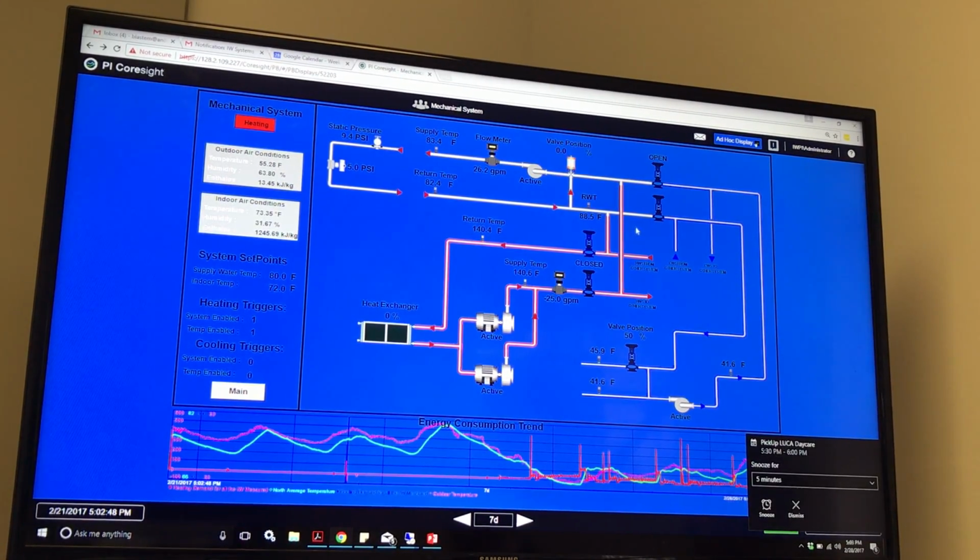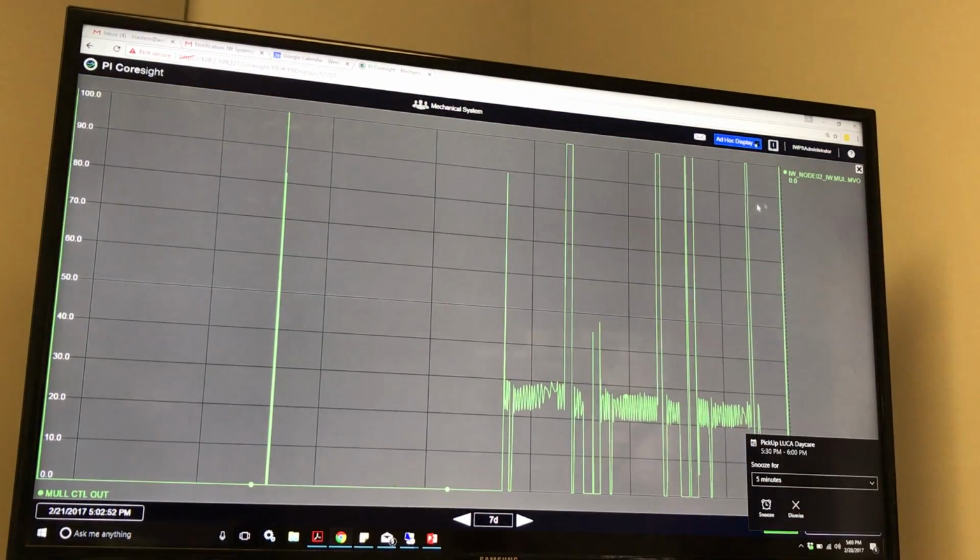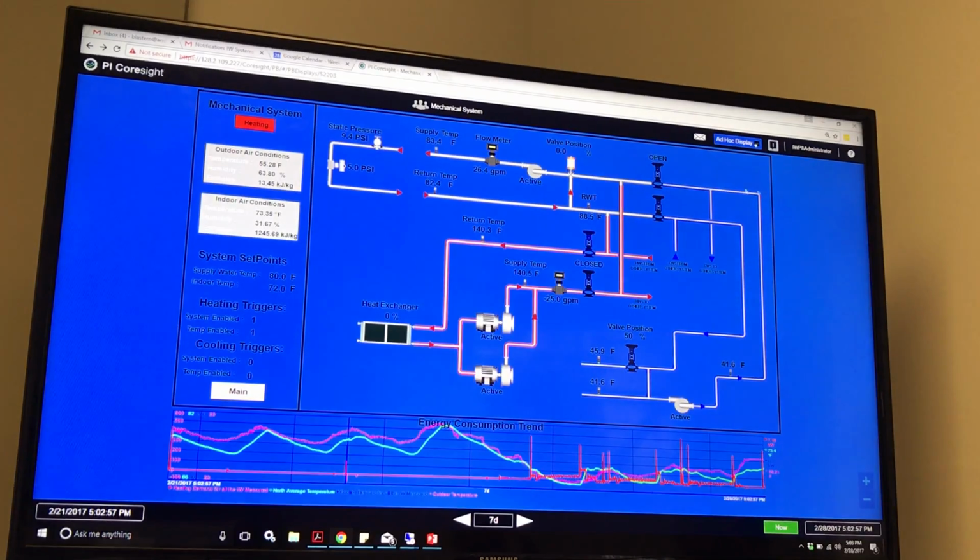It shows what's open and closed. This one actually shows me that the hot water is running and not the chilled water. But the value is within the data. The other one that you see has no data. It's instantaneous, so it's hard to find. So here I created open and closed. I can duplicate this in Aperture.